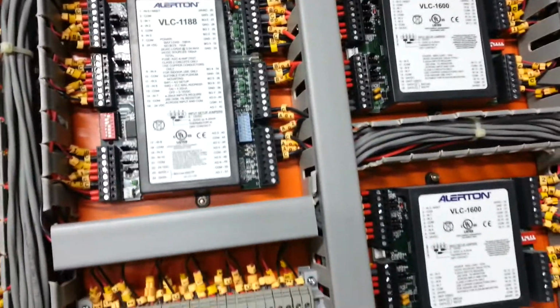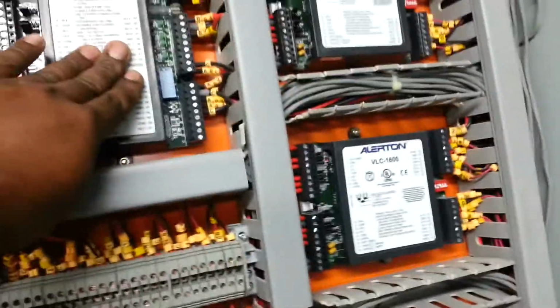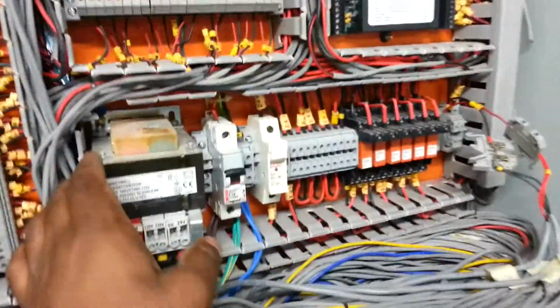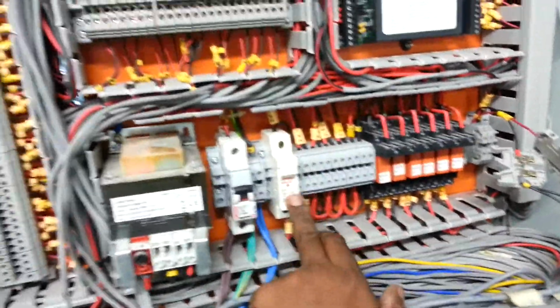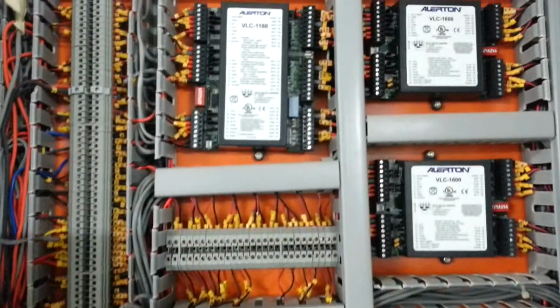Here is the panel for DDC. All these are DDC panels. This is the DDC panel control module. This is the AI module, analog input module, digital input module, analog output, digital output, like that. And here is the control transformer, the control fuse, and this is a breaker for the control transformer, control supply. Here there is another panel for DDC.